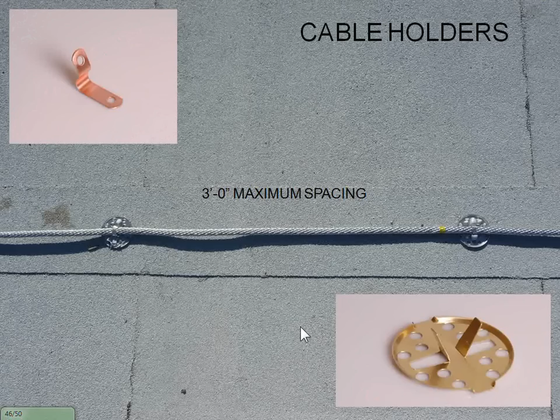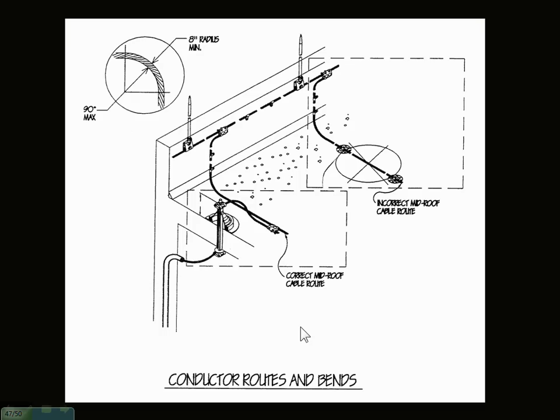Basically, lightning runs a lot like water. The reason is lightning can't go uphill, just like water can't go uphill. So when we're taking our lightning systems to ground, much like water, you're not going to run the piping back up and over. Lightning is the exact same way - every time we come down, it has to continue going down. So you want the cable to flow downwards; there's no way it's going to flow uphill.